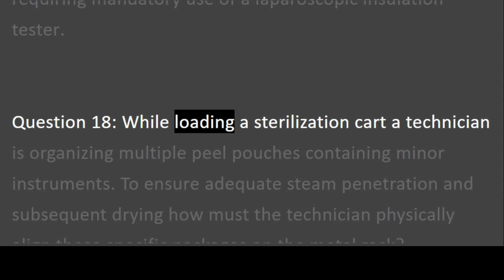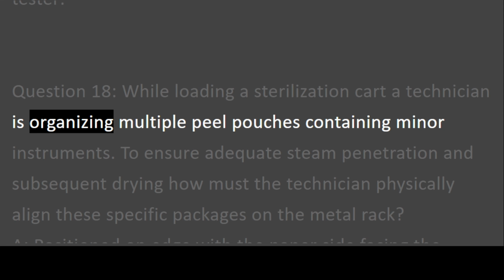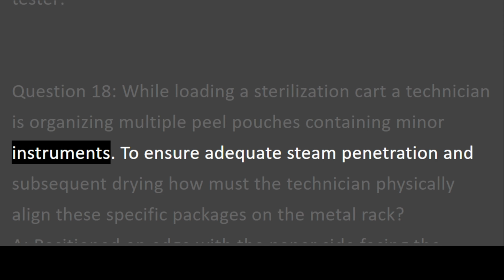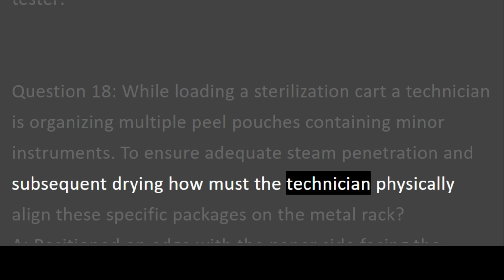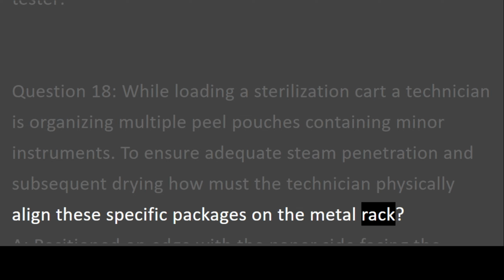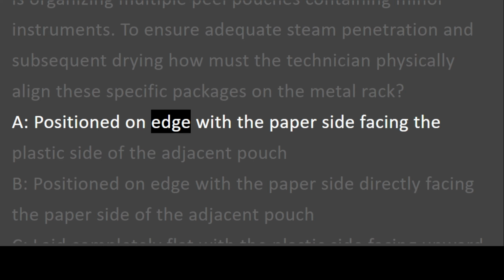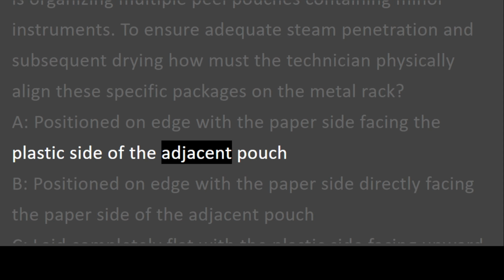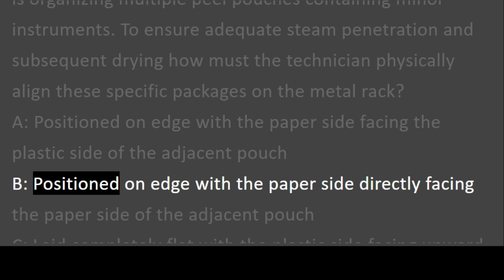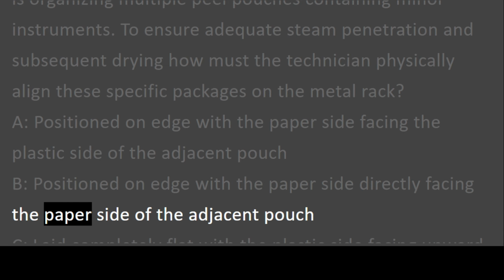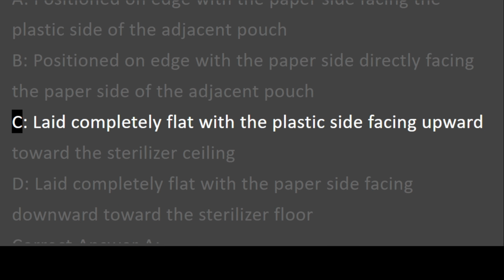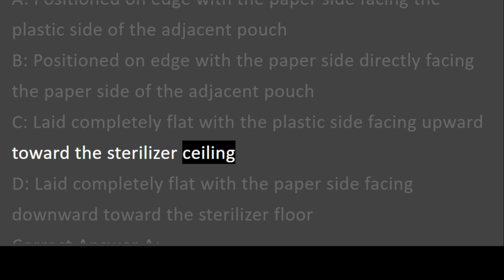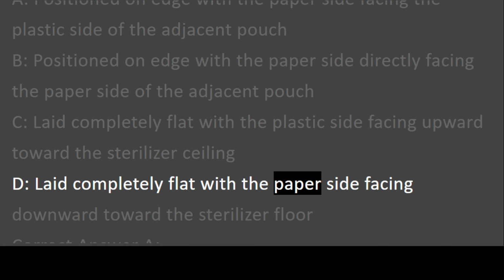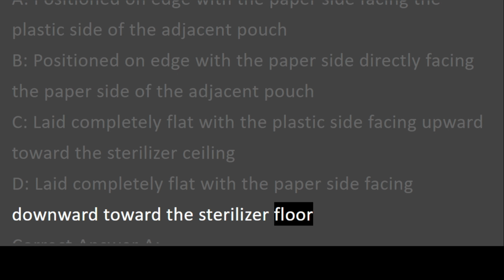Question 18. While loading a sterilization cart, a technician is organizing multiple peel pouches containing minor instruments. To ensure adequate steam penetration and subsequent drying, how must the technician physically align these specific packages on the metal rack? A. Positioned on edge with the paper side facing the plastic side of the adjacent pouch. B. Positioned on edge with the paper side directly facing the paper side of the adjacent pouch. C. Laid completely flat with the plastic side facing upward toward the sterilizer ceiling. D. Laid completely flat with the paper side facing downward toward the sterilizer floor.